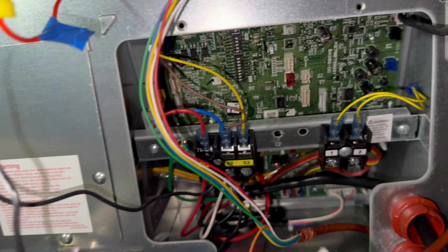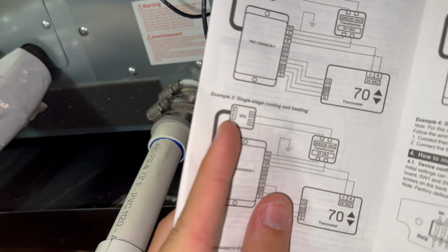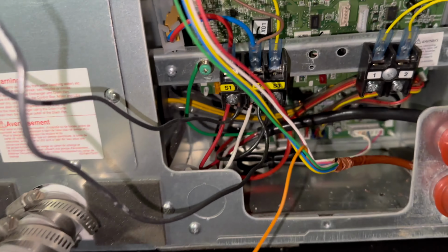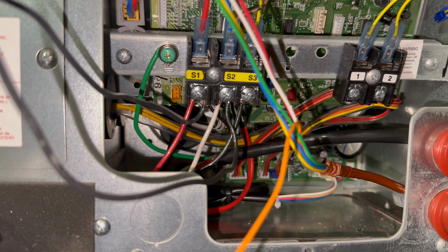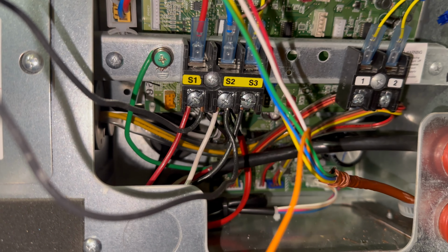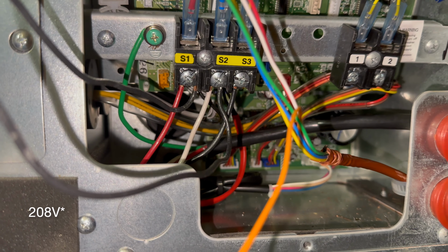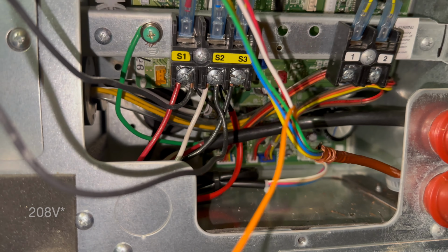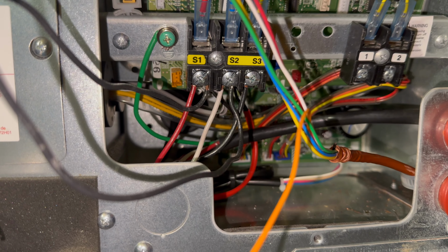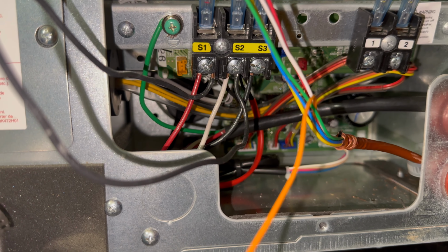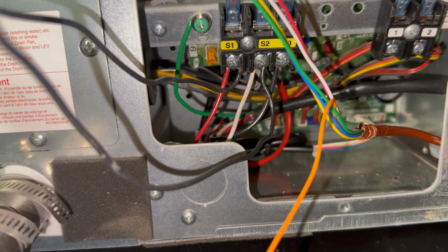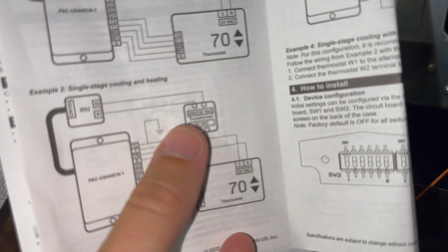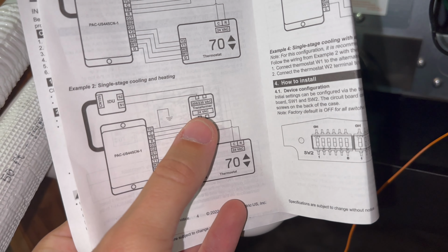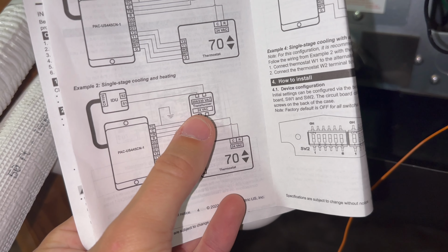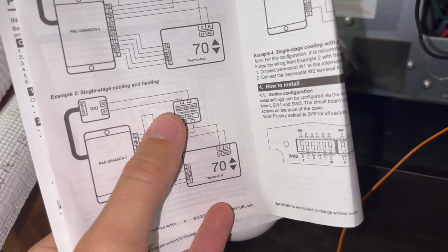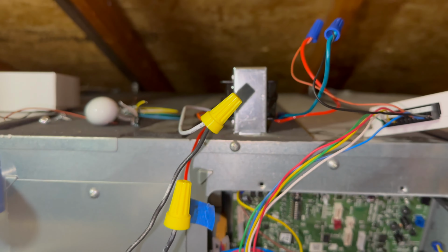On the IDU, which is just that circuit board, S1 and S2 are nicely labeled right here — these are your 208 volt power supply, so make sure your power's off and you're not touching that. This is where you'll connect your high voltage AC side to your transformer, which is right up here.